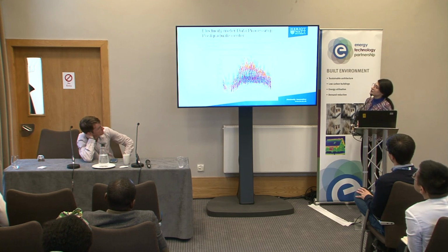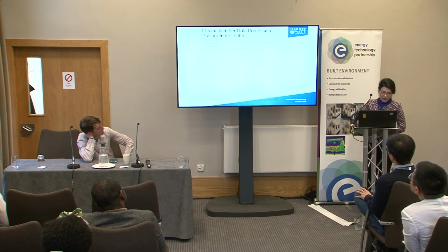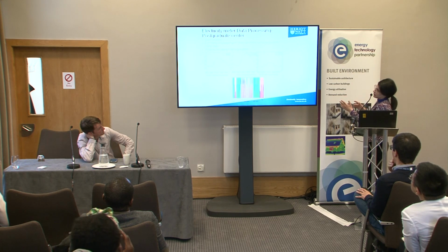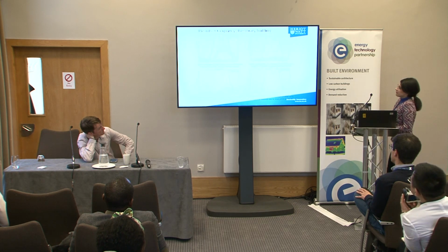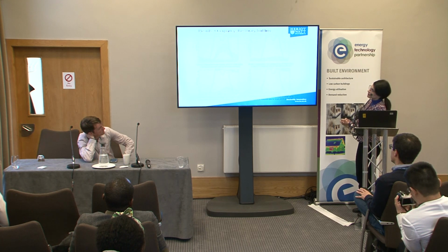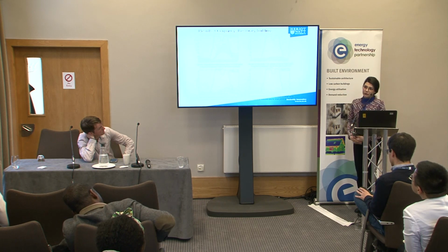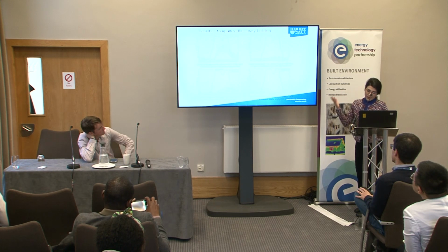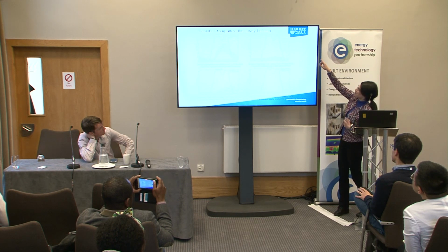For the electrical equipment in this building and lighting, I've used the meter data and used a clustering algorithm to create 3 sets of profiles for different periods of the year, and I've used these profiles in simulation to get better results. So if we calculate the numbers of occupants inside the building for the library building using occupancy density values and occupancy profiles provided by NCM, we end up with a profile that's like an M-shaped thing.